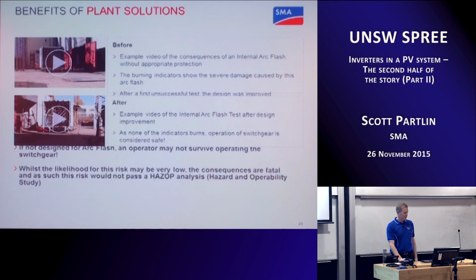Okay, so I included this slide mostly because it's got things that go bang, and that's always fun to show. So the benefits of plant solutions can be, once you get up to very large systems, very high voltages, the risk associated with those is much greater. And unlike at a residential or a commercial scale where you can work on the system when it's not live, at utility scale plants, because we don't like the lights going out, most of the work that happens at utility scale or on the distribution network needs to be done live.